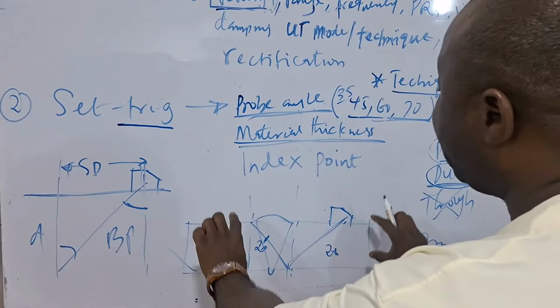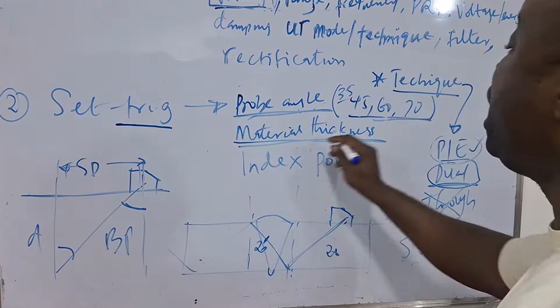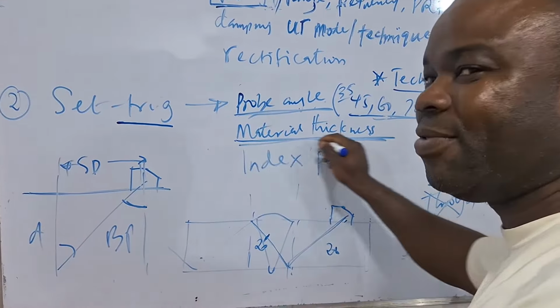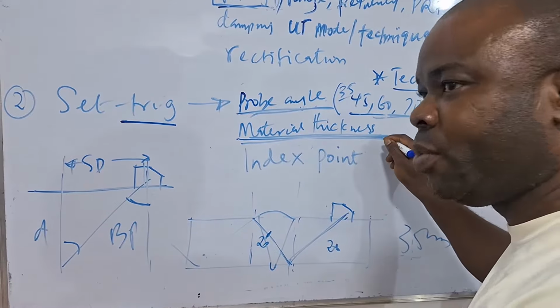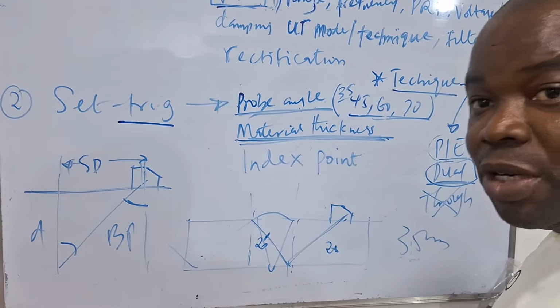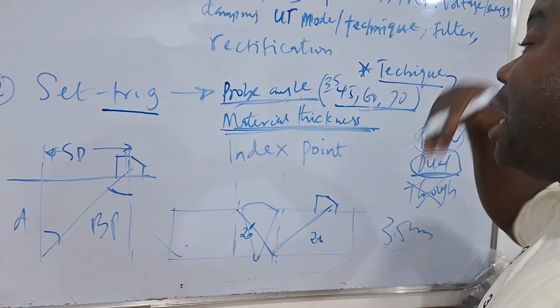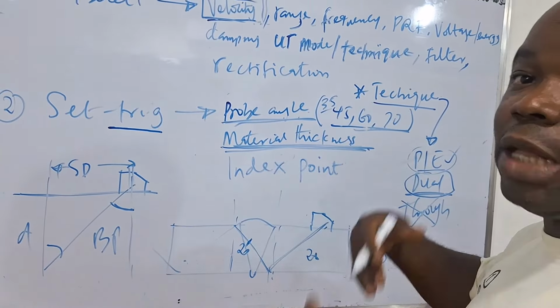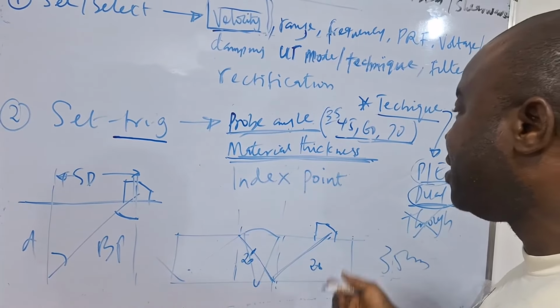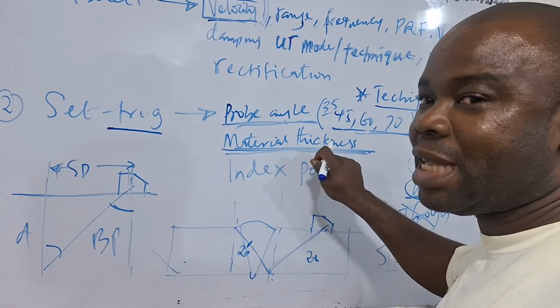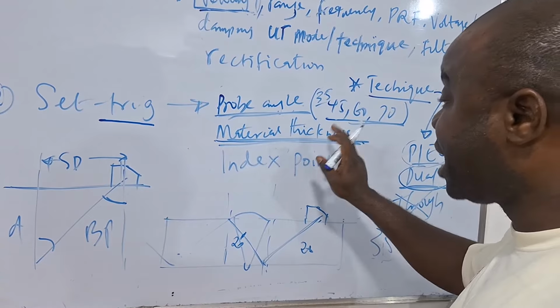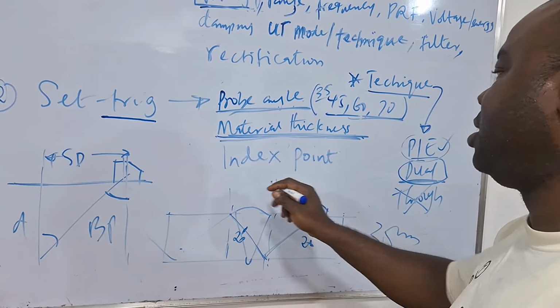So it is very, very key when you are doing angle probe to input the material thickness. Very, very important. Even if you are using a different calibration, maybe a calibration that you have saved, by the time you get to the field and you get the right material thickness, input the material thickness before you start scanning. Yes, you make mistakes.